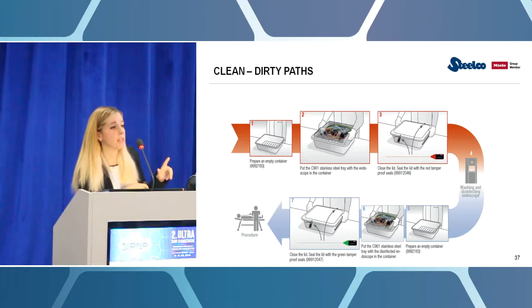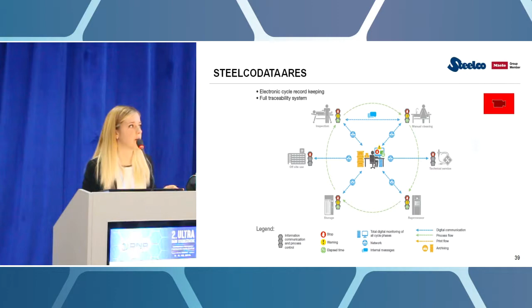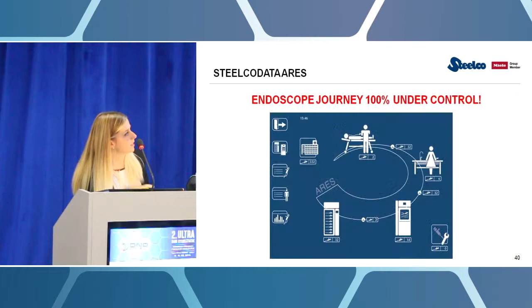And then we also have traceability solutions. Traceability solutions that can work at two different levels. You can decide to trace the cycle itself, or you can decide to trace the overall process of reprocessing of the endoscope. So in every single moment with this traceability system, you will be able to know exactly where your endoscope is. If it's being used on a patient, if it's, for example, being reprocessed inside an endoscope washer, if it's, for example, out for maintenance. So you will just have to interrogate your computer, and the traceability software will tell you exactly where your endoscope is. These are some interfaces of the traceability system, and then these are some accessories.